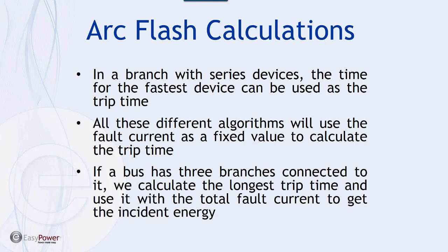Number two, you better come up with a system or a method or an approach or an algorithm, however you call it, that considers the change of current only because of the time progression, nothing else. We all know that the current changes because of the motors dropping by or protective devices tripping. But other than that, if nothing else in that circuit, in that one line, in that setup changes, the current by itself would change. So the approach has to somehow capture that change. In other words, it has to be an iterative method that once it goes beyond a certain threshold, let's say 5 cycles or 8 cycles or 9 cycles, automatically updates all the current values and then plugs in the new values to calculate the new trip times.